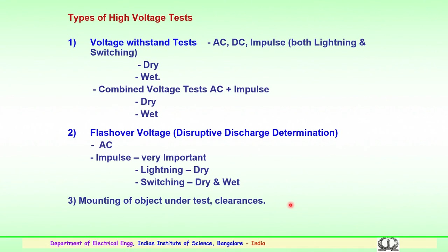So this is voltage withstand, whether the equipment will be able to withstand dry and wet conditions for AC, DC, impulse, lightning and switching surges. The second is the flashover voltage, or disruptive discharge, to determine the flashover strength of the insulation. Again here tests like AC for the rated voltage, whose values are determined by the standards, are applied. Again the impulse, lightning dry conditions, switching dry and wet conditions, all are very important and are generally applied, and the withstand for flashover for lightning and switching, both dry and wet conditions, is monitored. And apart from this, when carrying out the above tests in the laboratory, the mounting of the object and the clearances which are to be maintained are specified, and these are to be adopted for the correctness of the testing.